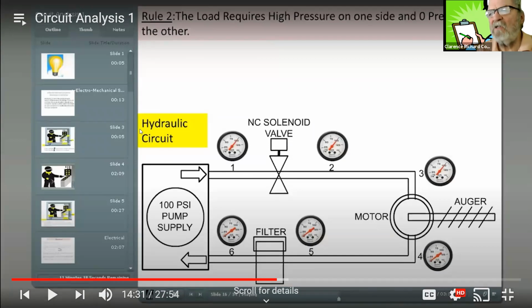The solenoid valve switch is turned on. The auger motor runs at half speed. So all gauges are correct except 4 and 5, which would read 50 PSI. That means there's a restriction between 5 and 6. Most of you got that. If you have 50 PSI there and 0 there, there's a restriction there. Very good.